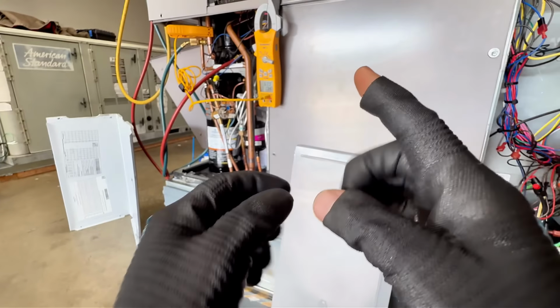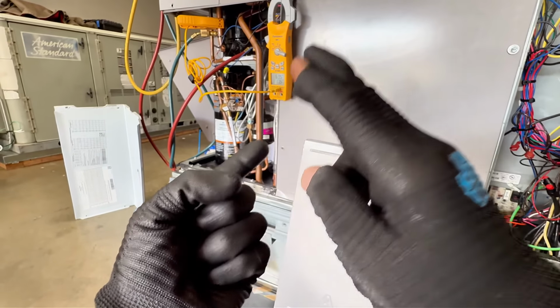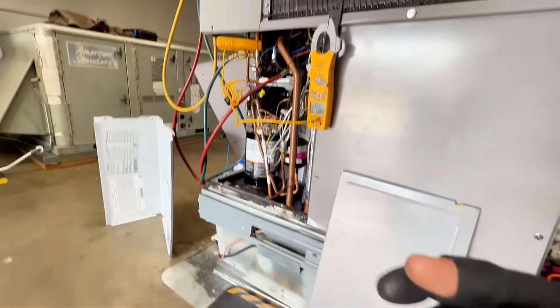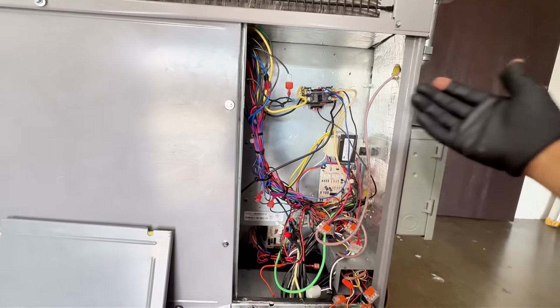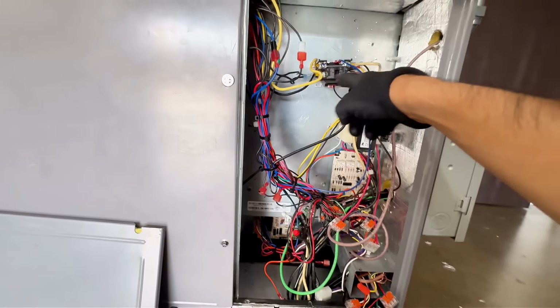So you've got to ask yourself, is it a power issue? Is it a high voltage or low voltage? Typically, it's not a high voltage issue because the contactor, if you've got 24 volts, it's going to go through. Could the contacts be pitted?